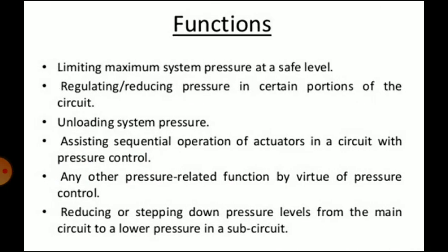So, the functions of pressure control valves. First is limiting maximum system pressure at a safe level. Second, regulating or reducing pressure in certain portions of the circuit. Third is unloading system pressure. Fourth, assisting sequential operation of actuators in a circuit with pressure control. Fifth is any other pressure related function by virtue of pressure control. And sixth is reducing or stepping down pressure levels from the main circuit to a lower pressure in a sub-circuit. So these are the functions of pressure control valves.